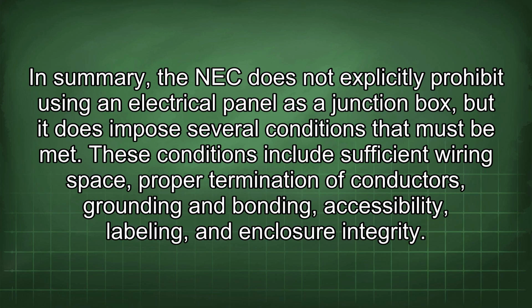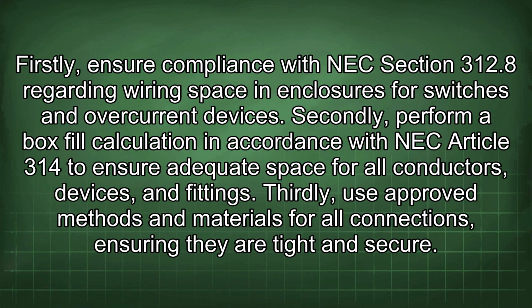These conditions include sufficient wiring space, proper termination of conductors, grounding and bonding, accessibility, labeling, and enclosure integrity. Firstly, ensure compliance with NEC Section 312.8 regarding wiring space in enclosures for switches and overcurrent devices. Secondly, perform a box fill calculation in accordance with NEC Article 314 to ensure adequate space for all conductors, devices, and fittings. Thirdly, use approved methods and materials for all connections, ensuring they are tight and secure.